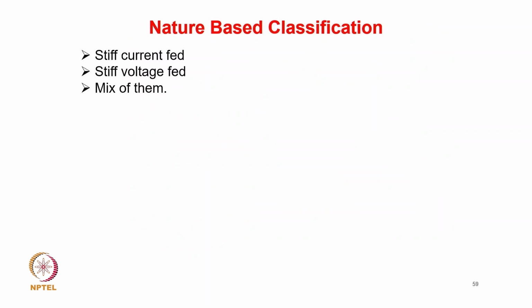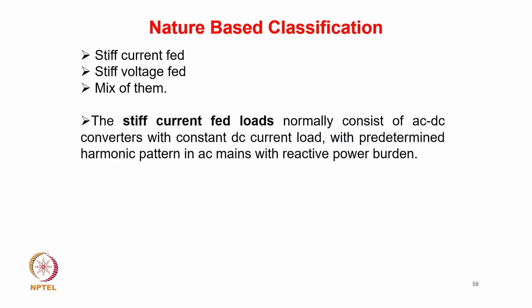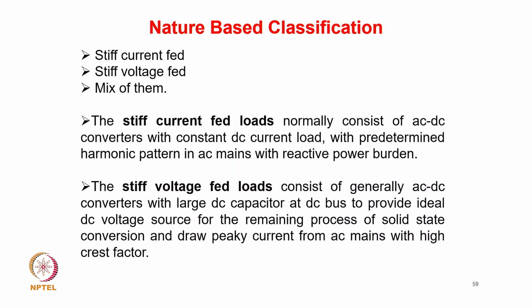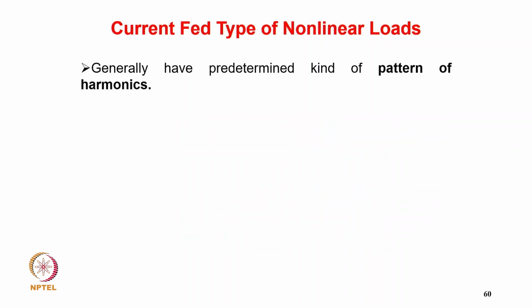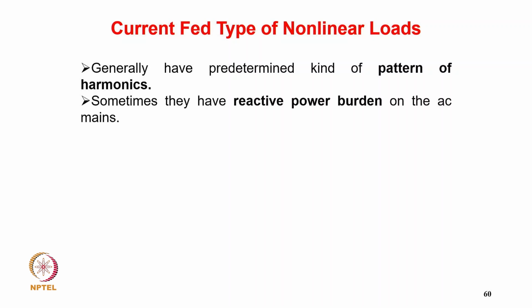Now nature-based classification: stiff current source, stiff voltage source, and mixed load. The stiff current source load normally consists of an AC-DC converter with constant DC current load, with a predetermined harmonic pattern in the AC mains and reactive power burden. The stiff voltage source load generally consists of an AC-DC converter with a large capacitor at the DC bus to provide an ideal DC voltage source for the remaining process of solid state conversion, and draws peaky current from the AC mains with a poor power factor. Generally they have a predetermined kind of pattern of harmonics.